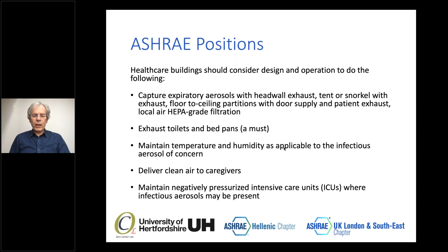More on the healthcare buildings. We need to maintain rooms with infectious aerosols where there's concern about these aerosols at negative pressure, and where we are absolutely sure, then we need to provide that negative pressure. And we need to provide 100% exhaust from the patient rooms. We need to use UVGI, ultraviolet germicidal irradiation, and we need to increase the outdoor air change rate in patient rooms from 2 to 6 air changes per hour. We also need to establish HVAC contributions to a patient room turnover plan before reoccupancy. So suppose that we had a patient in a room infected with COVID-19. The patient has then left the room. That room needs to be treated by HVAC contribution before reoccupation by a new patient.